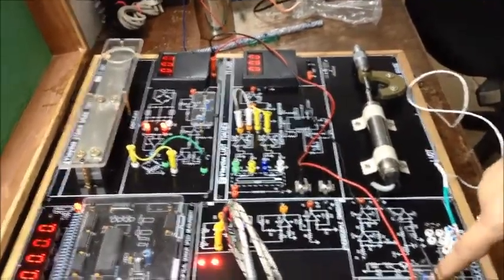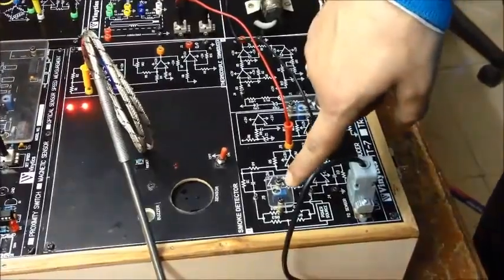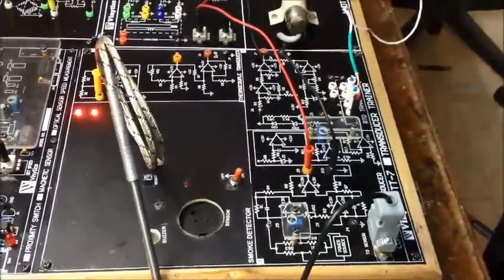As you can see, here are two trim pots. One is for zero setting and one is for span settings. The holes are provided on the top so that you can adjust it with respect to your requirement.